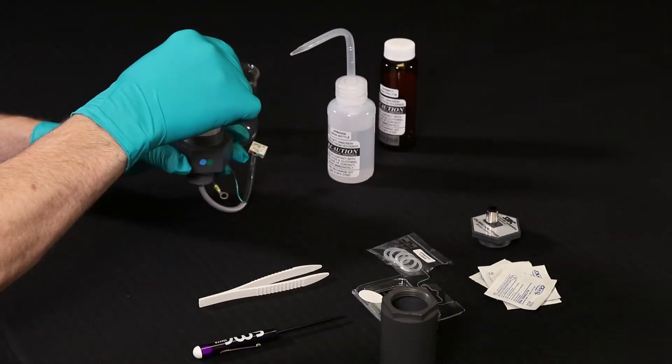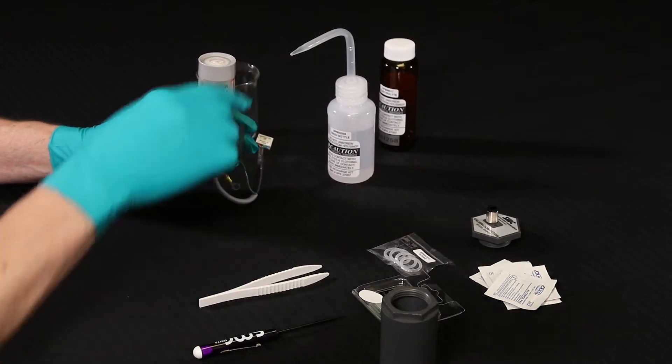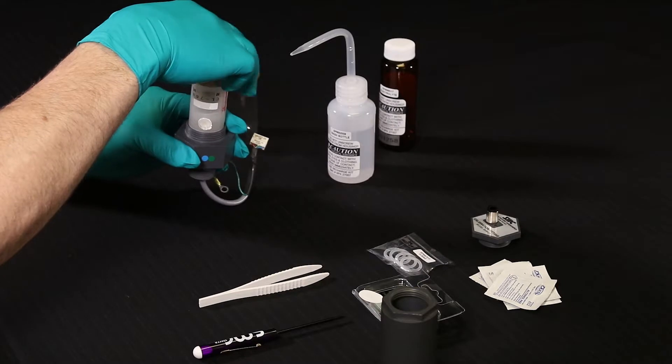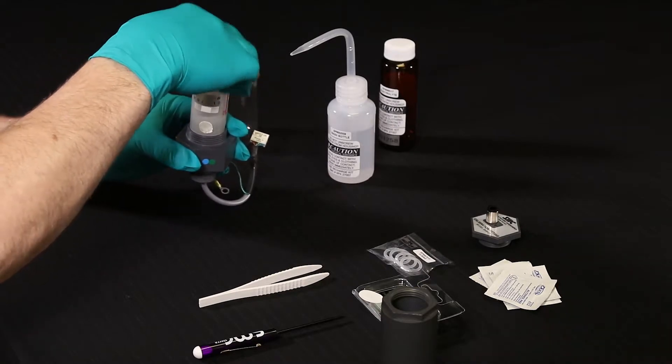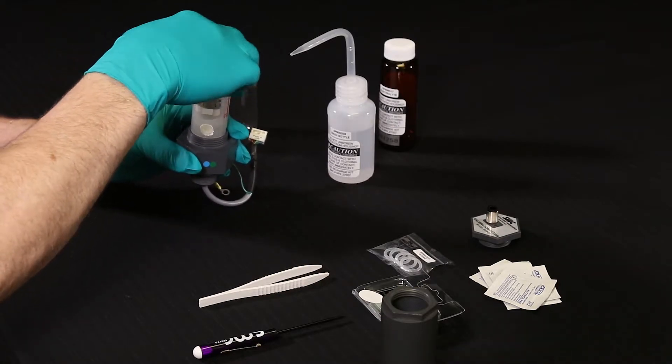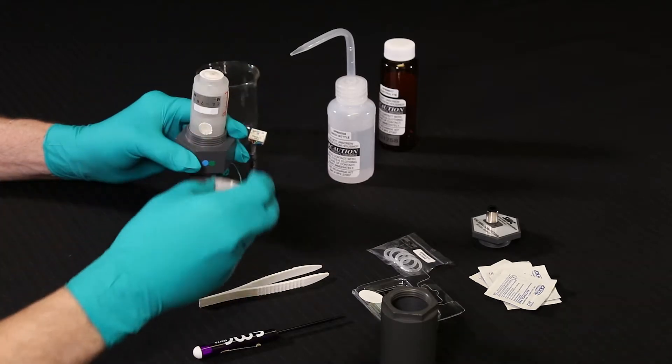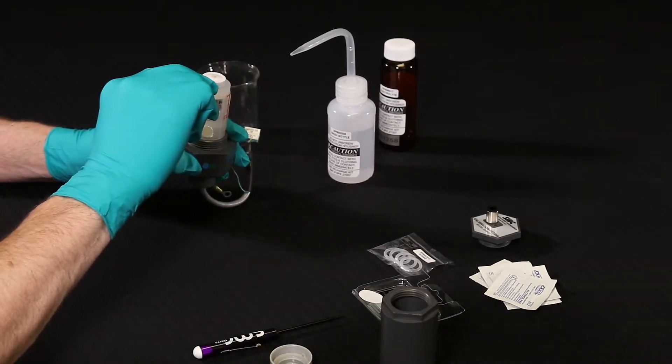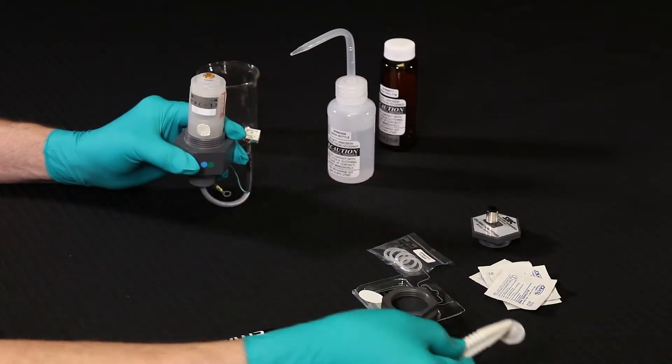Then, invert the sensor assembly so the membrane is facing upwards. Afterwards, unscrew the box nut and remove the retainer ring to expose the membrane. Be sure to remove the old membrane and the O-ring using the tweezers and dispose. Make sure that you do not touch the membrane or the O-ring with your fingers.